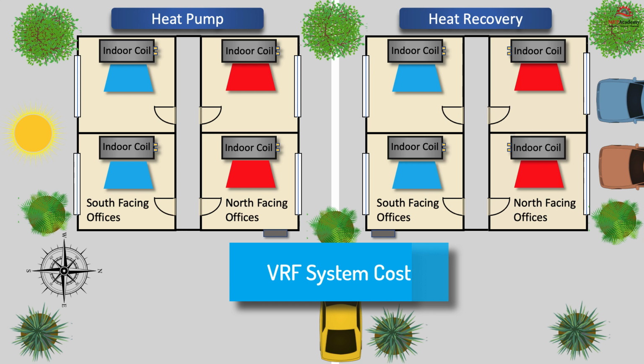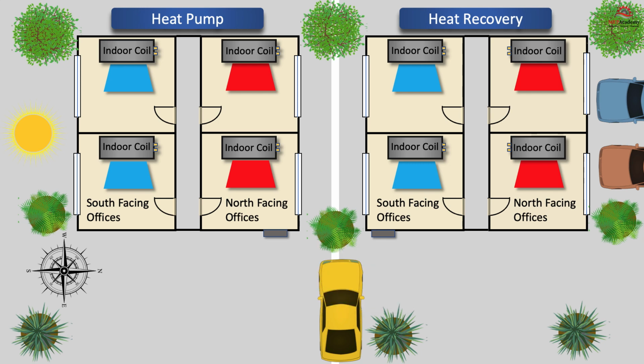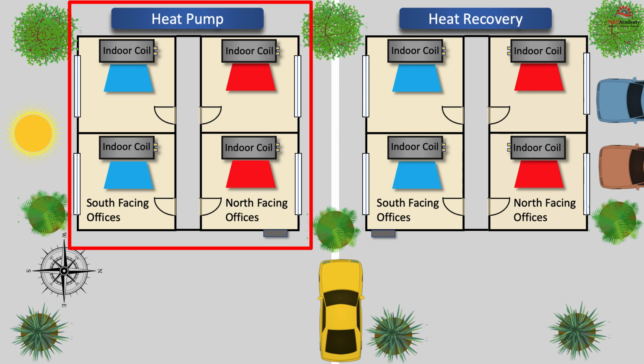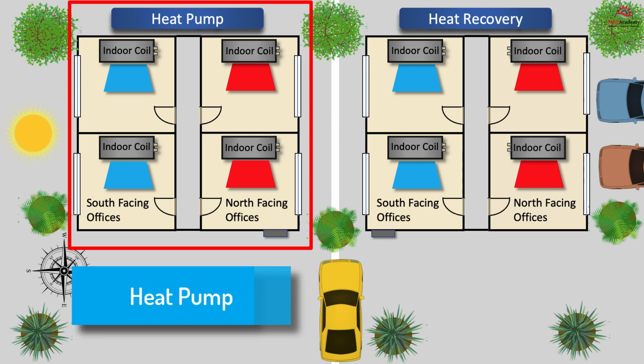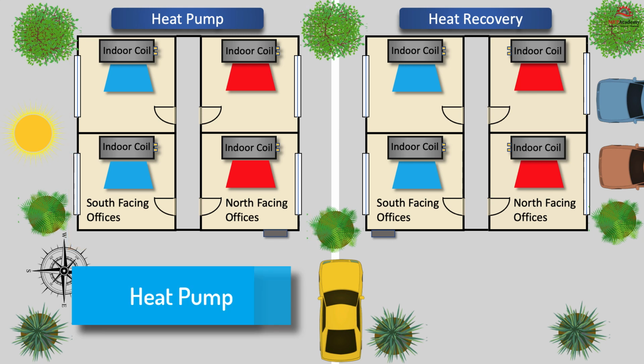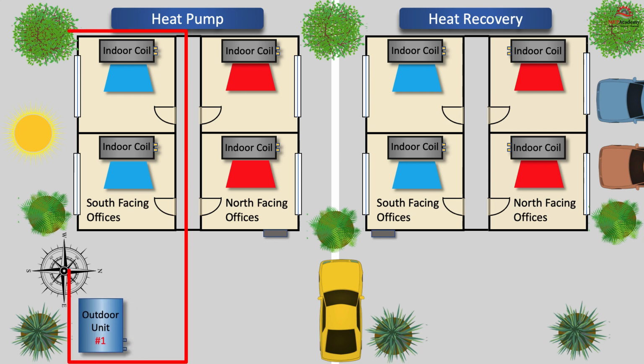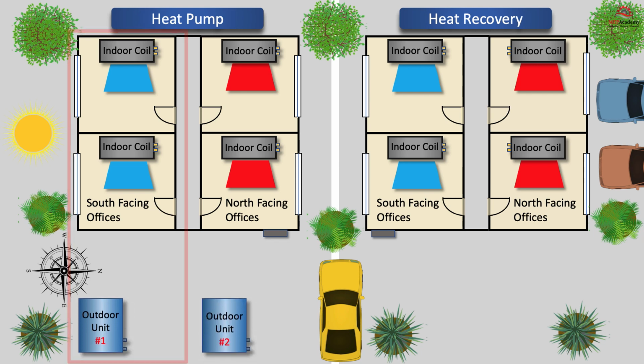To determine which system is more expensive, an analysis will have to be done. If we have 2 small identical office buildings as shown here, with the first building using a VRF heat pump system, the heat pump system would require at least 2 outdoor units, one for the south exposure and the other for the north exposure.